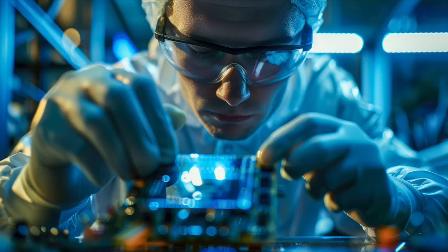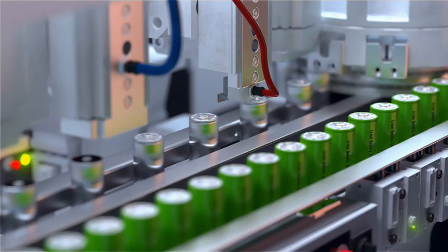OK, what type of processes are we talking about that would need humidity control? Well, it could be whenever materials are sensitive to moisture loss or gain, they would need air humidity that was in balance with their moisture content. This then stops them drying out or absorbing moisture from the air. Or it could be a certain humidity level is needed to cause a reaction, like paint or glue curing, or even stop a reaction.